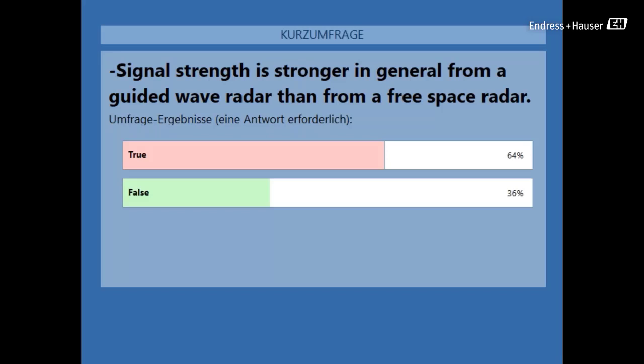If I have one HART output in the guided wave radar, could I read from the device level and interface, or do I need two outputs from the radar to do that? Matthias, want to take that? Sure. So the answer is no. If you take HART, you have a primary value, secondary value, third value, and fourth value. You can use a HART multiplexer and get 4 signals out of the device through HART, so you don't need a secondary 4-20 milliamp output.